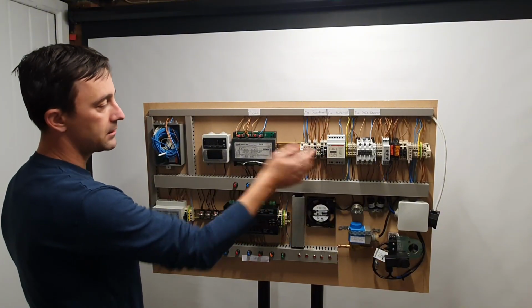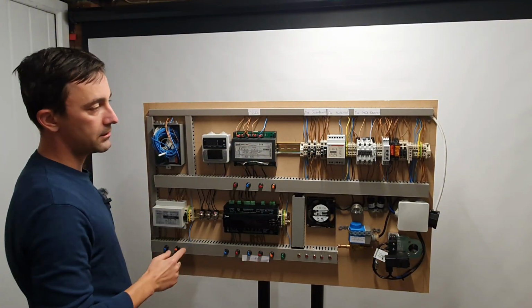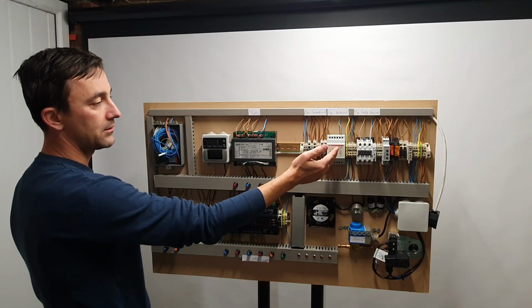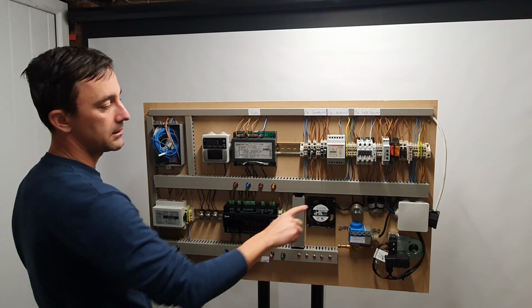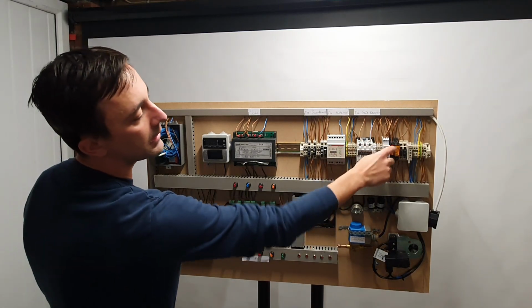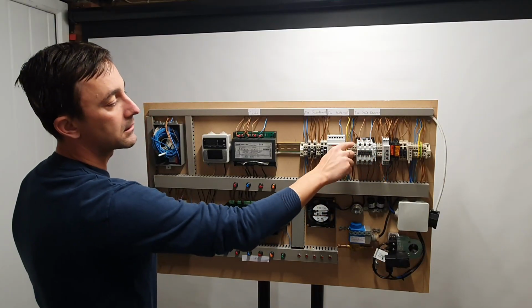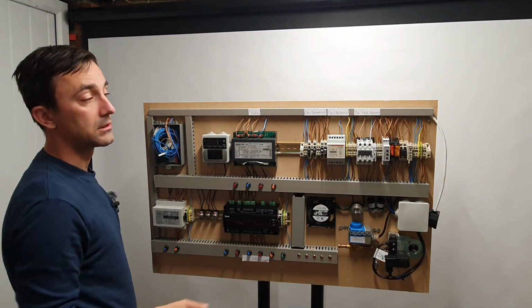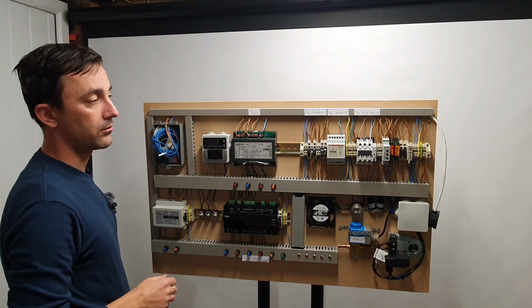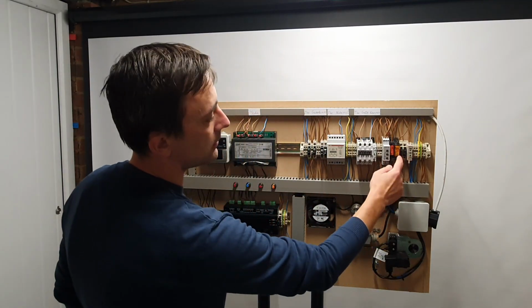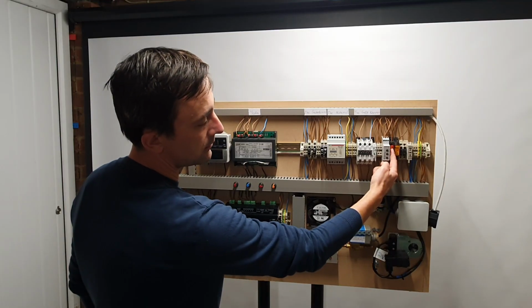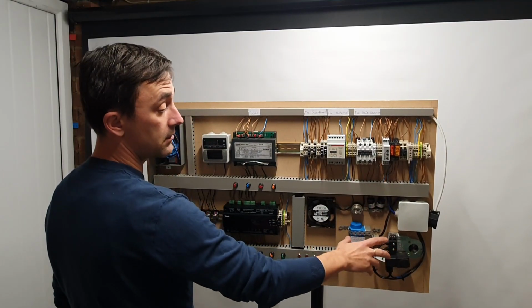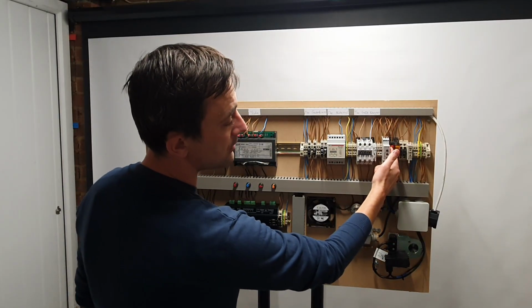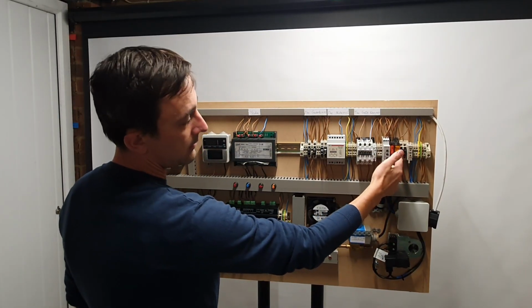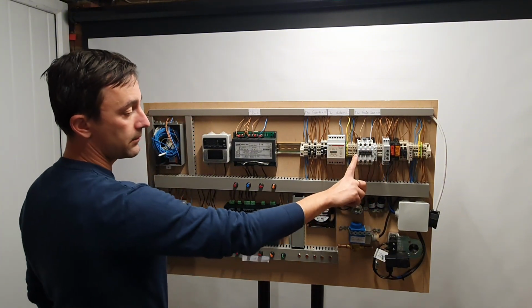we've got our fuses. Each controller has its own fuses. We've got a transformer, a 24-volt transformer. That's because the safety circuits and the relays and the compressor contactor, they run on 24-volt AC. So I had to install a 24-volt transformer. We've got a safety circuit relay. So if my safety circuit is healthy, this relay would be energized. We've got our compressor relay, and then obviously our compressor contactor.